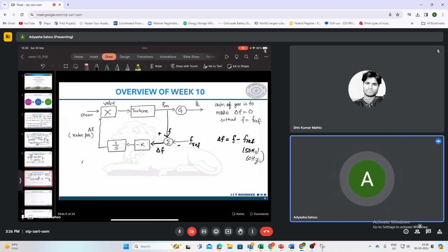So if this delta F is greater than 0, which means that your current frequency is greater than your reference frequency, what do we need to do here? Do we need to increase the generation or decrease the generation? If the frequency is greater than the reference frequency, we need to decrease the generation, right? PG needs to be reduced. So it will give the delta E to close the valve. Not all, some, according to how much quantity is given by this isochronous governor.